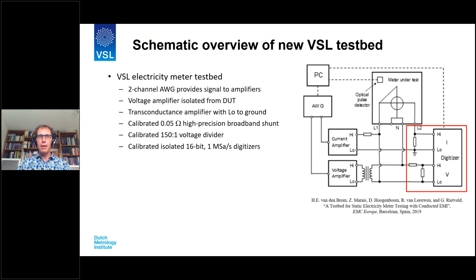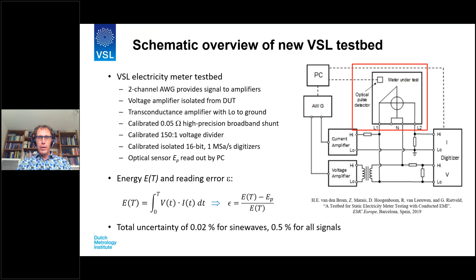So apart from calibrating the individual components, the setup has been independently validated by comparing the waveforms recorded to the waveforms sent to the generator memory, and by comparing the results of the test bed to those obtained using the original setup with real loads, as presented a few slides before. Okay, and in the meantime, we have tested a lot of meters with this test bed and also the benchmark meter that I presented in the previous slide. So that's why I know that this benchmark meter is also good.